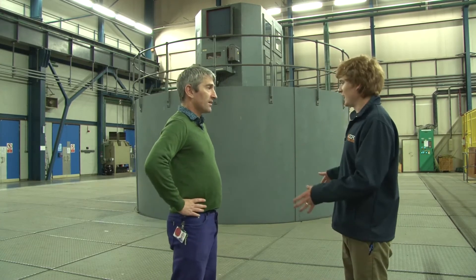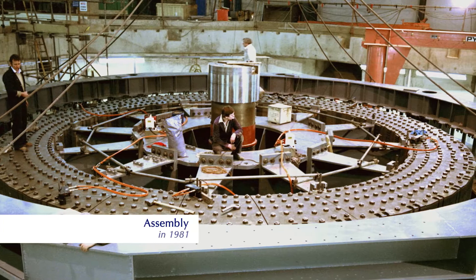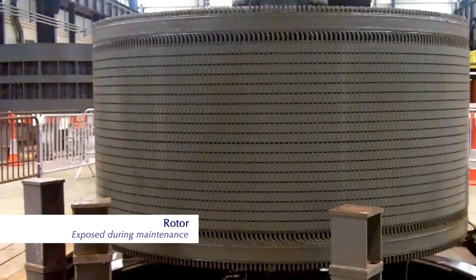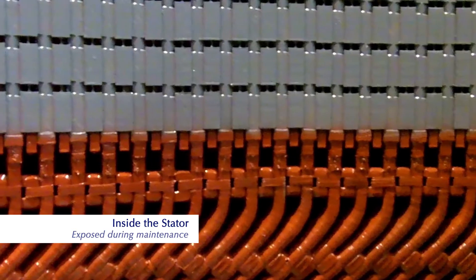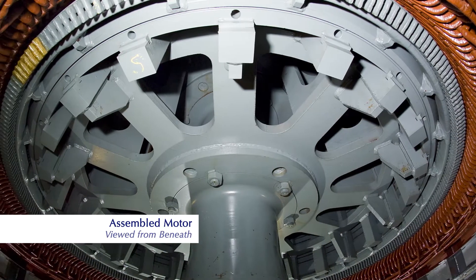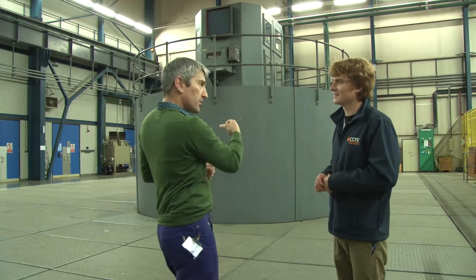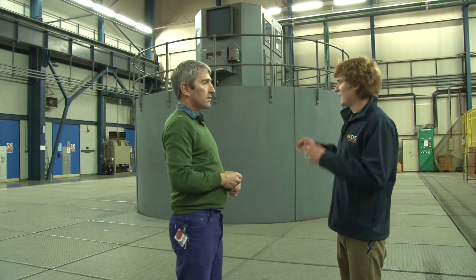That's right, yes. What we've got here is 700 tons of circular disc spinning round really fast at about 200 RPM. That's why we're vibrating so much. What's driving that? This is a very large electric motor in here. It's similar to when I was pedalling the bicycle - it accelerates our flywheel up to those speeds. It's as if the bike is lying on its side and the cluster's sticking up here. When you're pedalling, you'd be supplying power to that which makes the wheel go round.